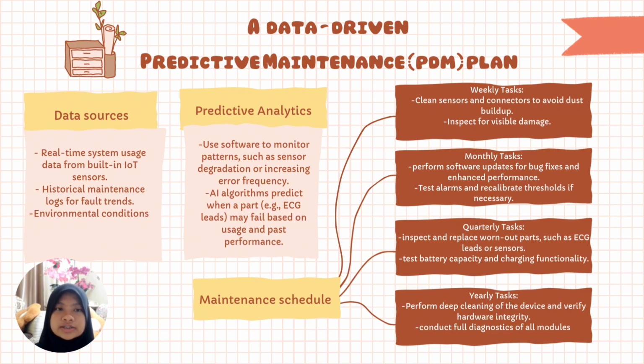For quarterly tasks, inspect and replace worn out parts such as ECG leads or sensors, and test battery capacity and charging functionality. And lastly, for yearly tasks, perform deep cleaning of the device and verify hardware integrity, and conduct a full diagnostic for all modules such as display, ECG, and SPO2.